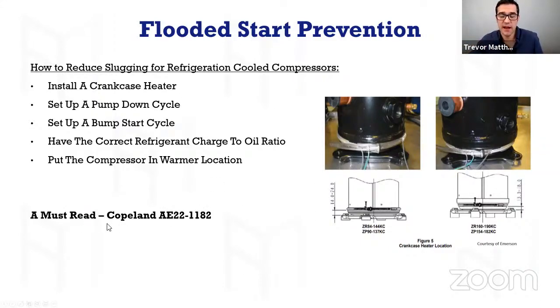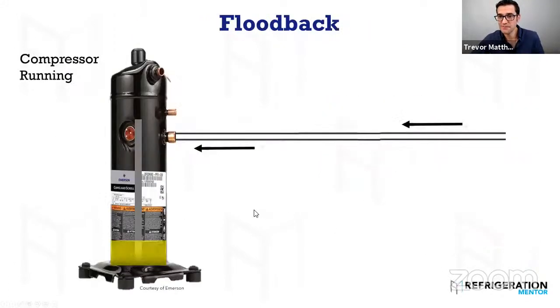And a must read is Copeland AE22-1182. You need to read this one. This is a guide talking about controlling liquid refrigerant in refrigeration and air conditioning systems. I did a podcast with Brian Orr from the HVACR school. Listen to that podcast. I talk about this whole manual because it's important to understand if it's a floodback, flooded start, slug, whatever it is, or an oil issue causing that issue. So floodback is the next one.